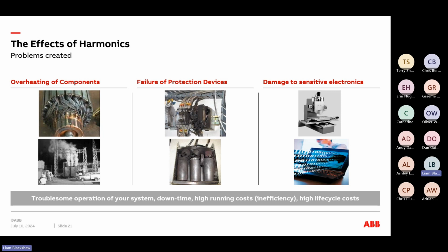And the key message is that without addressing these harmonics, you could have troublesome operation of your system, where as a result you might have failures and breakdowns, so you have some form of downtime. You could also have high running costs because you have an inefficient system, and over the course of an equipment or system's life cycle, those life cycle costs may start to get high and increase. In some cases you could also get penalised by the distribution network operator, the DNO. They could penalise you for having high levels of harmonic content on your system, they could give you a penalty, and in some cases they could have the right to cut off supply to your system, to name but a few things.